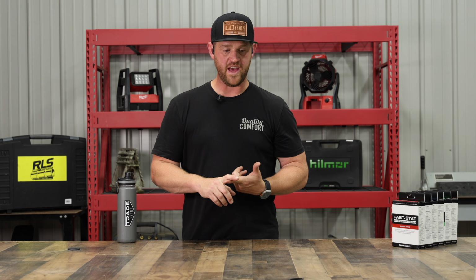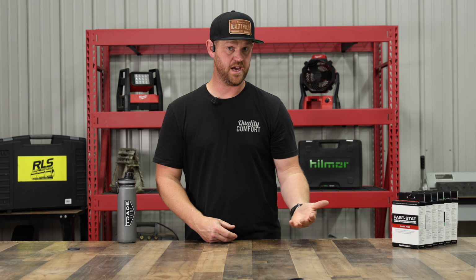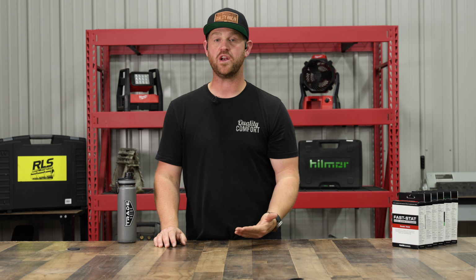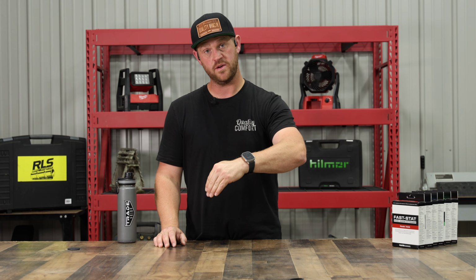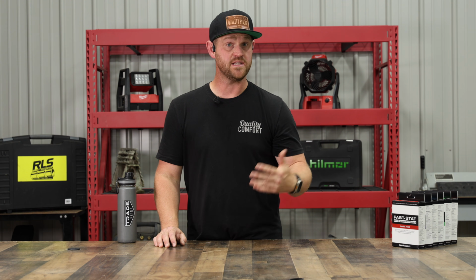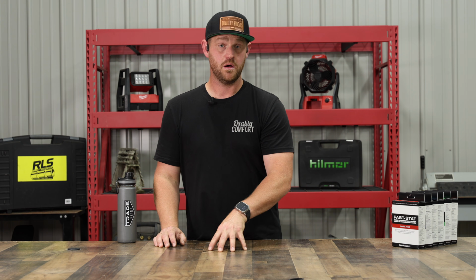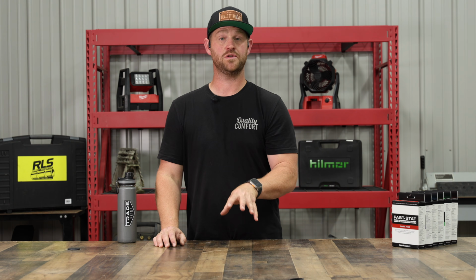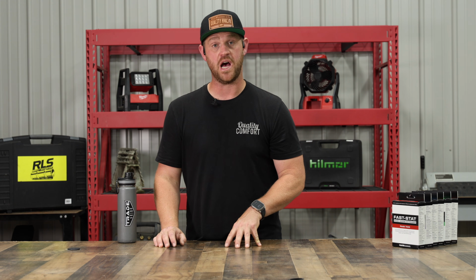And then going back to power consumption. So one thing we deal with in Tennessee, we have a lot of heat pump systems. And on normal single stage equipment, you're going to have an electric heat as your backup heating source, because a conventional single stage heat pump starts to lose heating capacity a lot once it gets about freezing outside. So once it gets below 40 degrees, your heating capacity starts to drop off, and then it relies on that electric heat as a supplement to be able to heat the house properly. The problem with that is that electric heat costs a lot to operate. So that's why you might be used to very high electric bills in the wintertime if you have this type of system.